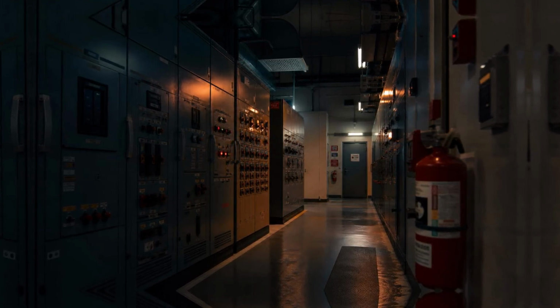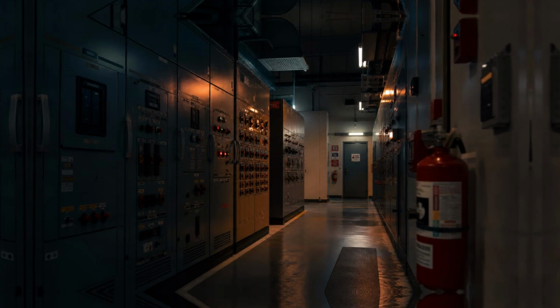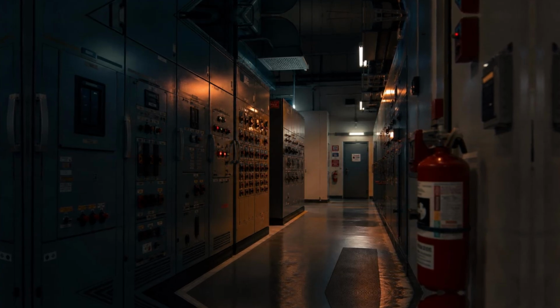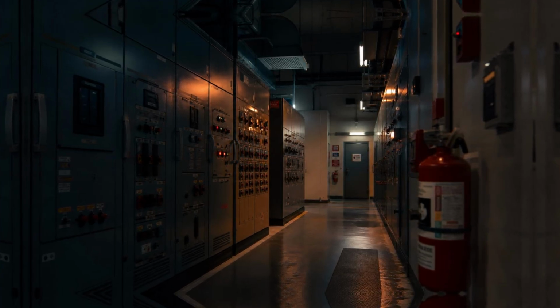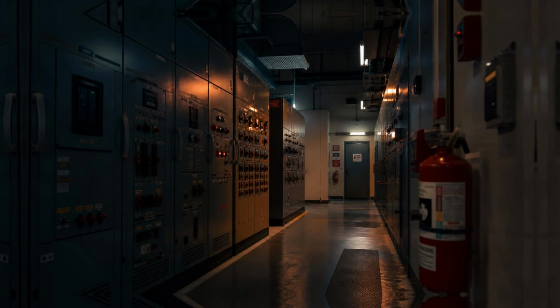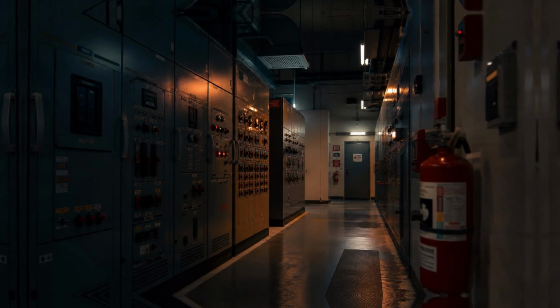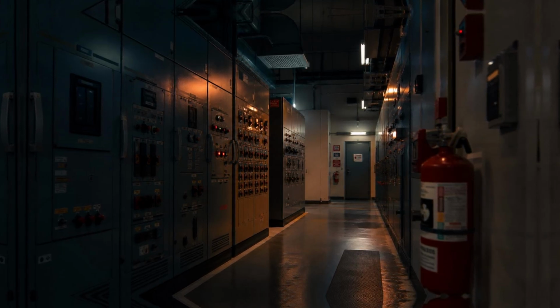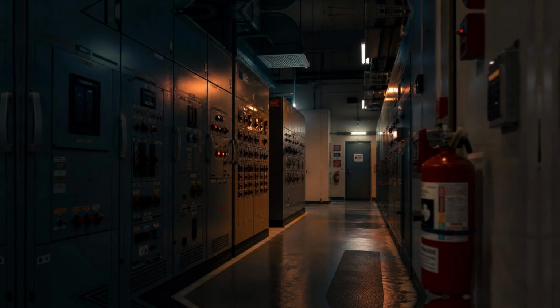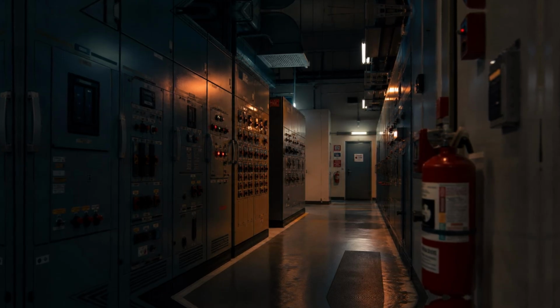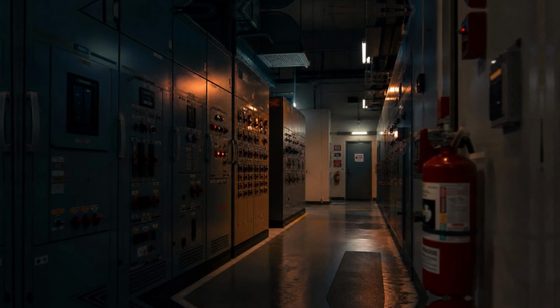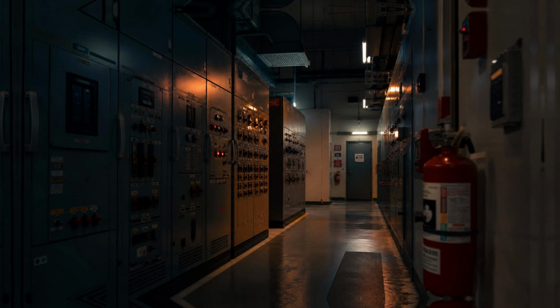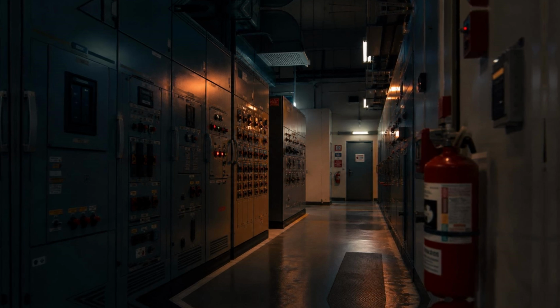generator under conditions designed to verify that it will start, that it will come up to speed, that it will produce acceptable voltage and frequency, and that it will sustain operation through the duration of the test. There are different kinds of exercises, and they serve slightly different purposes. A no-load exercise runs the generator without connecting it to any building loads.